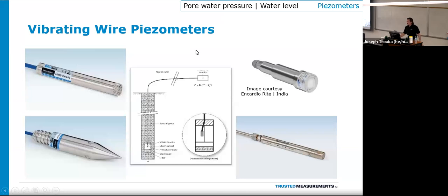Top right here is a heavy duty type piezometer. These exist for very high pressure applications, 20 MPa, often in tailings dams where you may have some movement, some shearing. It just gives a little more support to the instrument itself. And then the bottom right here is a high temp piezometer for geothermal applications. They can be used up to like 250 degrees C, very hot applications.